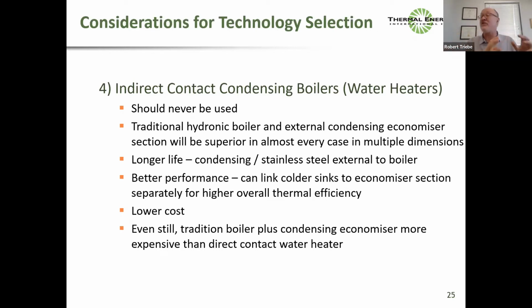The traditional boiler and condensing economizer combo has a longer life because the hydronic boiler will last forever, and the condensing stainless steel section is external to the boiler. It's got even better performance. You wouldn't think so, but I'll weave the tale of why we get better performance by having the boiler and the economizer separate. I'm hoping some of you are surprised by me saying a condensing hydronic boiler won't deliver the same. Yep.